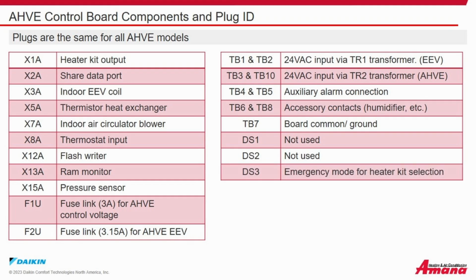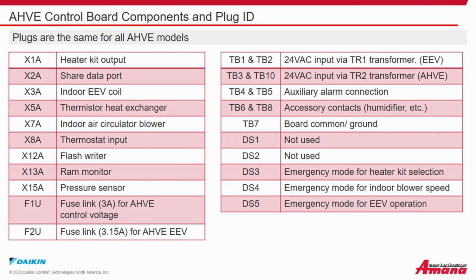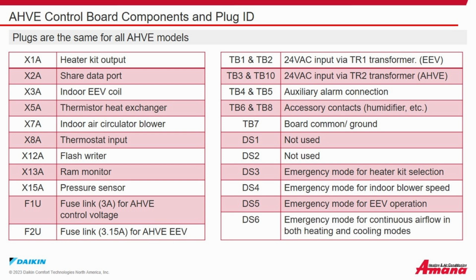Dip switch 3, emergency mode for heater kit selection. Dip switch 4, emergency mode for the indoor blower speed. Dip switch 5, emergency mode for the electronic expansion valve operation. Dip switch 6, emergency mode for continuous airflow in both heating and cooling modes.